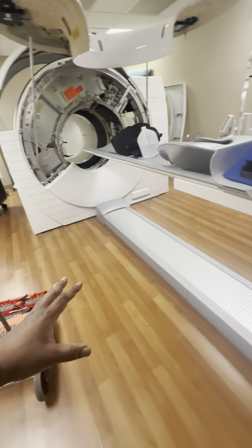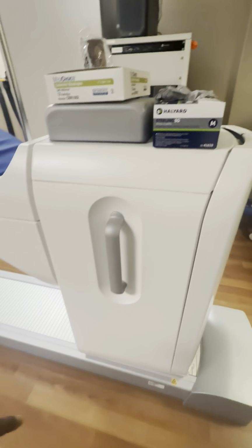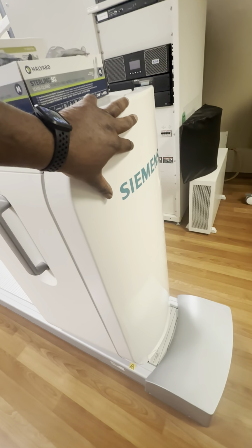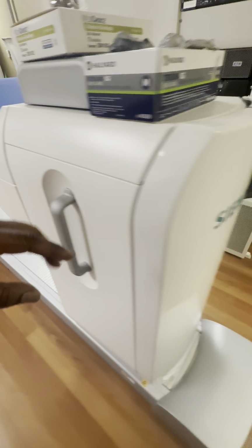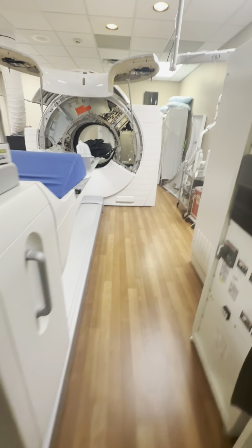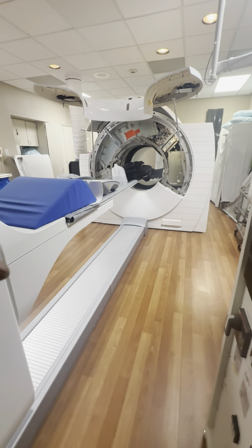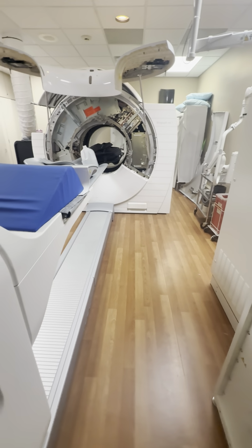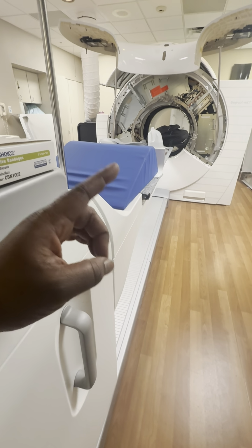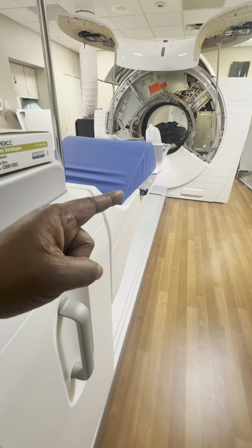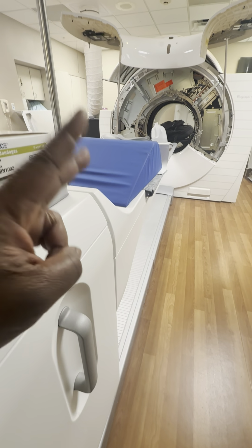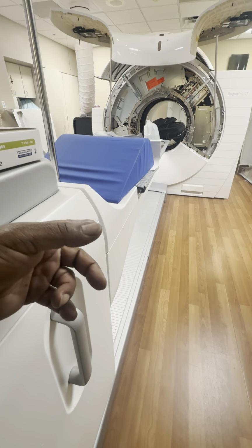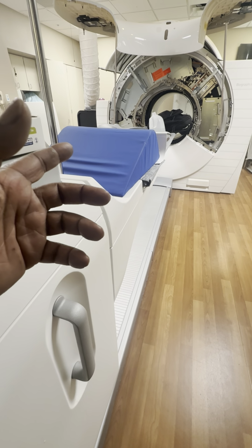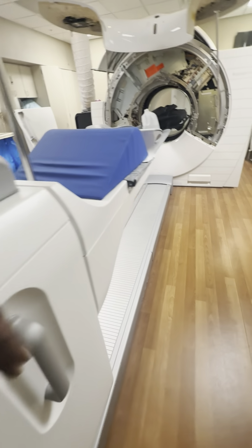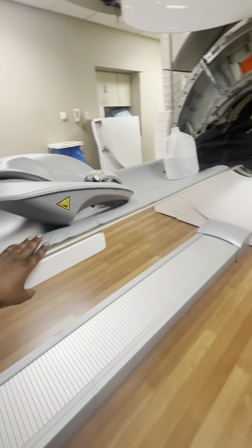Unique to this system, it has a table where all the electronics are back here in what's called a backpack, and it rides on a magnetic rail. It's unique to the Biograph, which I say of PET systems. Most CTs have a standard table. If it's Siemens, it's either the PHS systems or the mCT, multi-purpose table, which allows for a carbon fiber tabletop, which is this part right here.